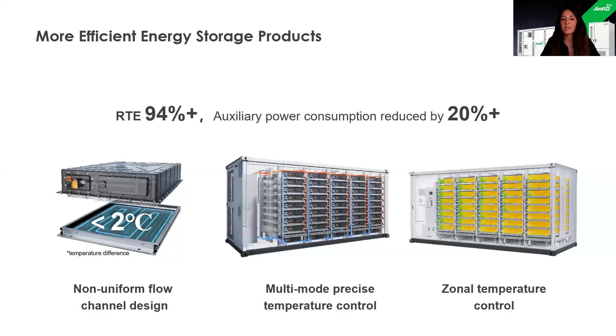Here's how the liquid cooling system works. Every single pack, the black drawer I mentioned before, has inside a circuit through which liquid coolant flows, which is 50% aqueous and ethylene glycol. Depending on whether heating or cooling is needed, it goes to a heat exchanger to provide heat or cooling to the battery, maintaining the battery temperature between 20 and 30 degrees Celsius.